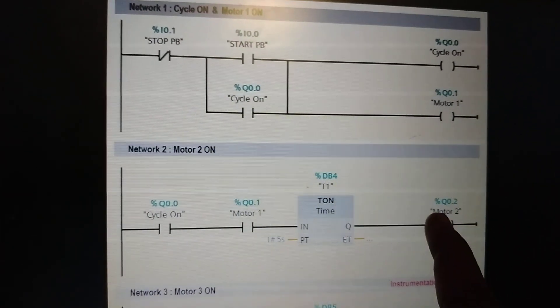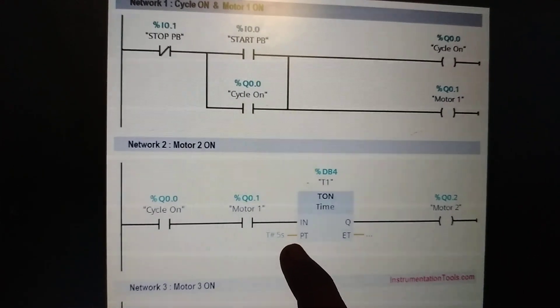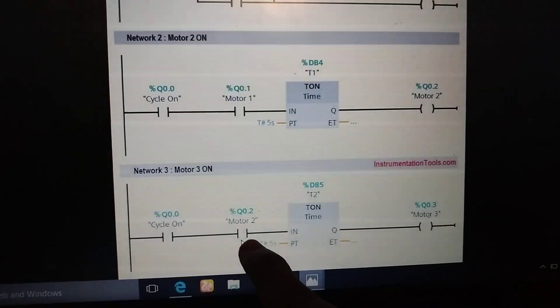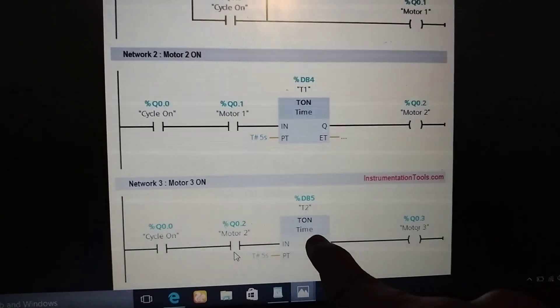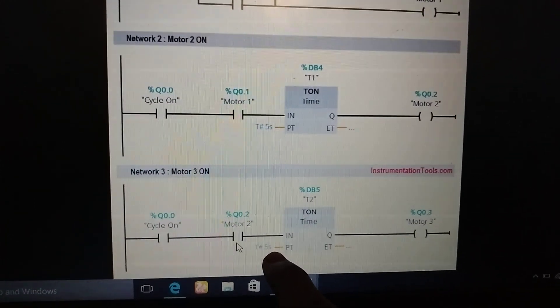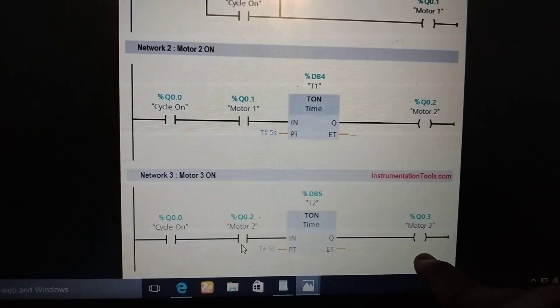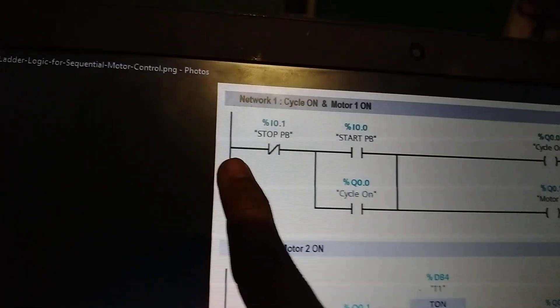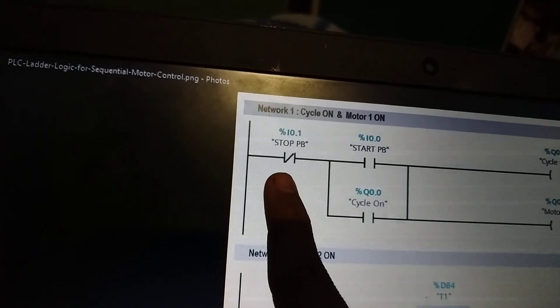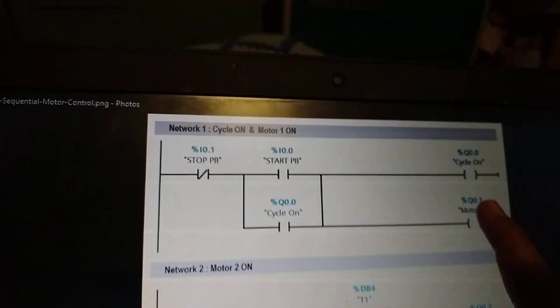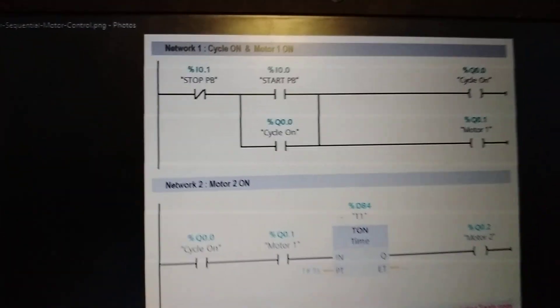This timer makes motor two start after the five-second delay period, and then motor three starts after a further delay. A normally open contact of motor two is used here. When the stop push button is pressed, the normally closed contact is activated, which turns off the cycle and also turns off all the motors. This logic provides a basic idea about applications of PLC in controlling motors sequentially.